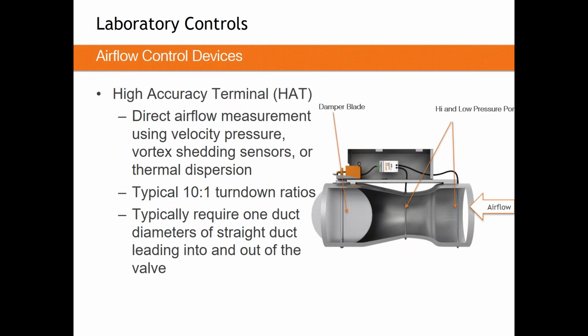Extremely similar to a VAV box is a technology we call a high accuracy terminal. The high accuracy terminal, for all intents and purposes, is a VAV box. It's just a better VAV box. What it does is measure a higher pressure drop through the device, giving it a little bit more accuracy and a little bit more repeatable accuracy. So with a high accuracy terminal, we'll show you one example here. This is the Antec Controls version. Our product name would be the VFX.